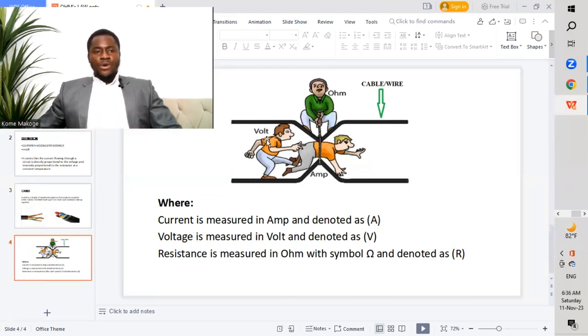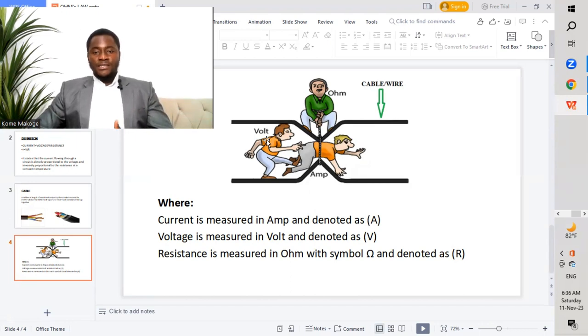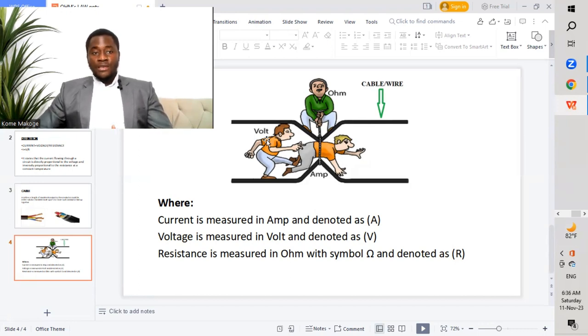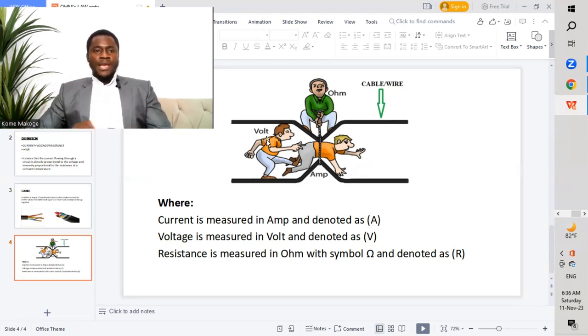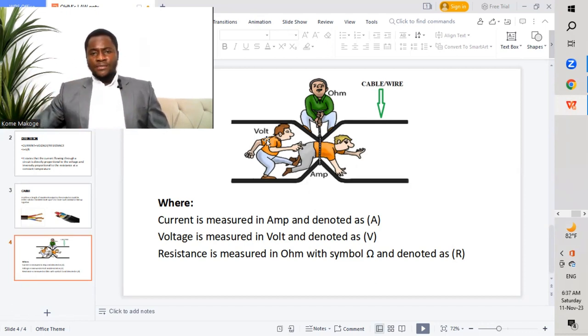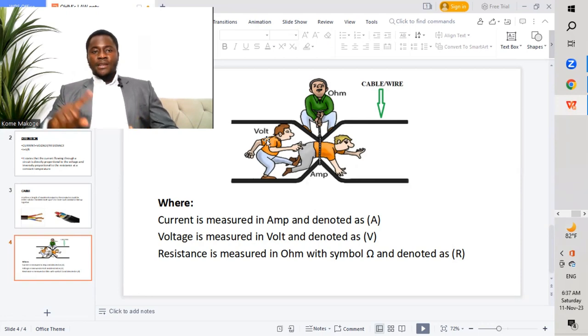When we do our design calculations, we determine our design current, taking into consideration different parameters such as derating factors and safety factors. Then we do our selection of cable or wire. After that, we select an appropriate size of protective device to protect that circuit. This selection ensures we meet Ohm's Law, which states that the current is directly proportional to the voltage and inversely proportional to the resistance at a constant temperature.